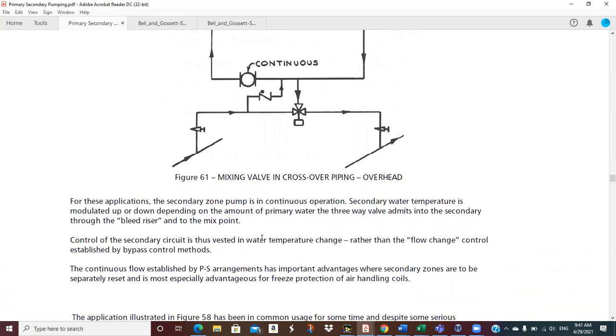Well, let's see, what do we got here for the applications? Secondary zone pump is in continuous operation. Secondary zone water temperature is modulated up or down depending on the amount of primary water that gets admitted to the secondary. Control of secondary circuit is just vested in water temperature change.